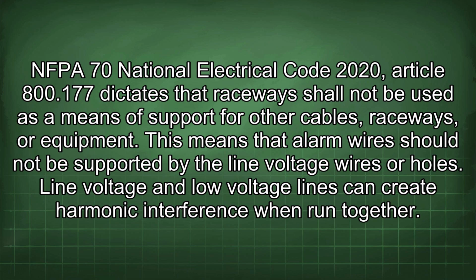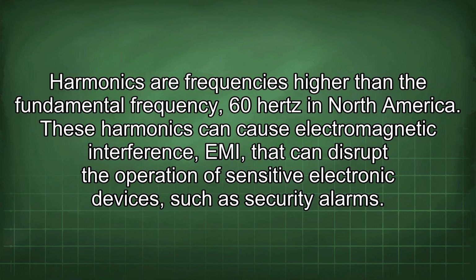Line voltage and low voltage lines can create harmonic interference when run together. Harmonics are frequencies higher than the fundamental frequency, 60 Hz in North America. These harmonics can cause electromagnetic interference (EMI) that can disrupt the operation of sensitive electronic devices such as security alarms.